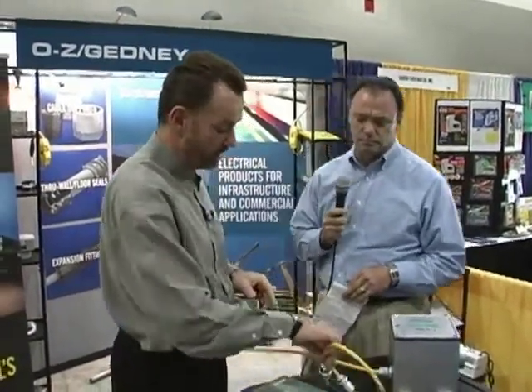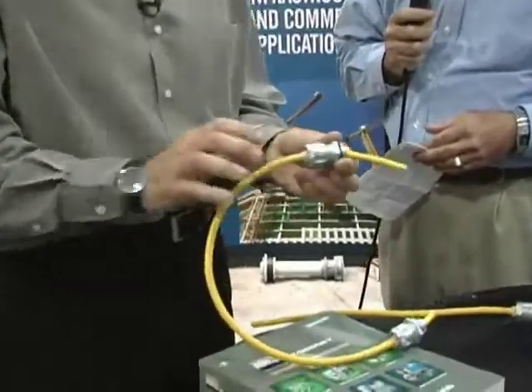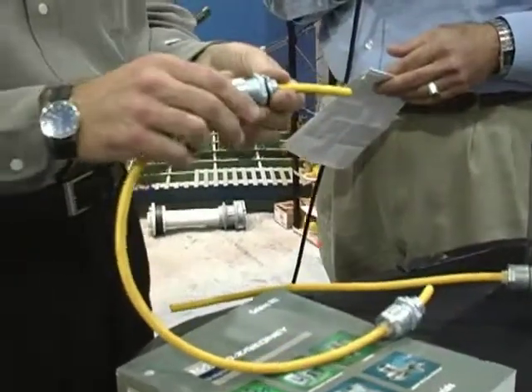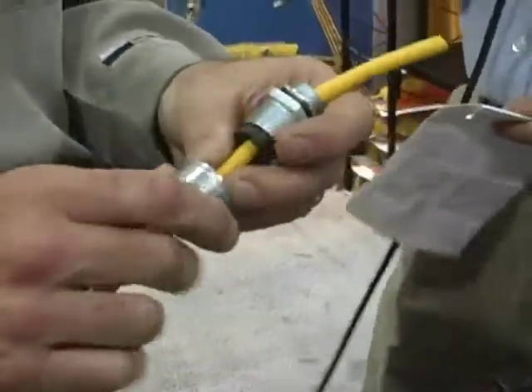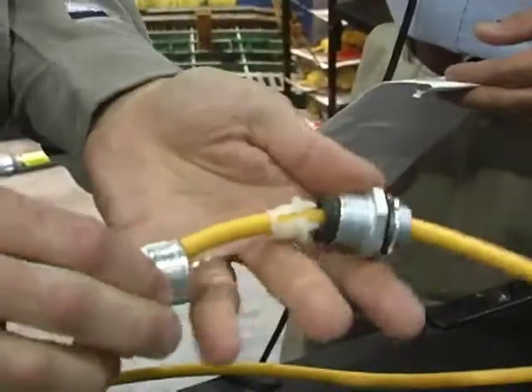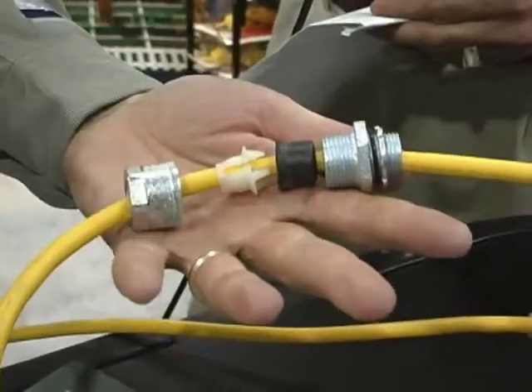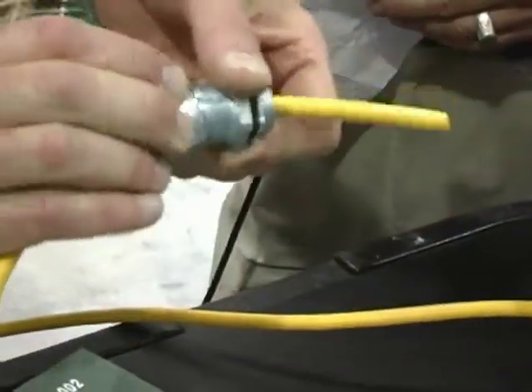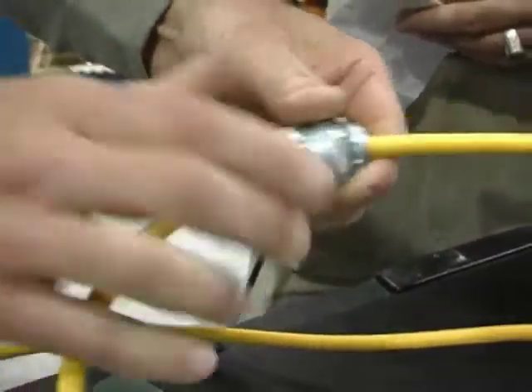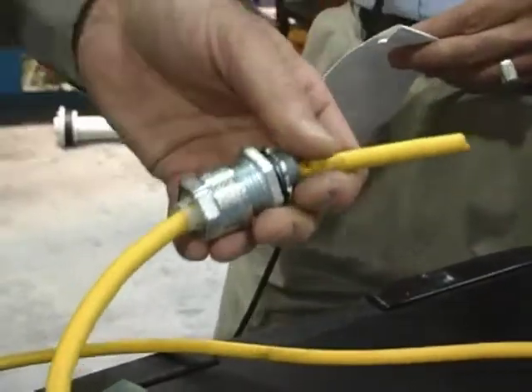A couple of products we've been talking about — here's something that is very simple, but the design from O-Z/Gedney is unique. This is a cord grip for a cable cord installation going into a junction box. What O-Z/Gedney has done differently is come up with what we refer to as our nylon grip design. You can see that little nylon gripper right there, the rubber grommet, and then the body of the fitting. When I tighten down this nut onto that cable, that nylon gripper is going to squeeze down and grab onto the cord, just like the teeth in a drill chuck when you're putting a drill bit in.